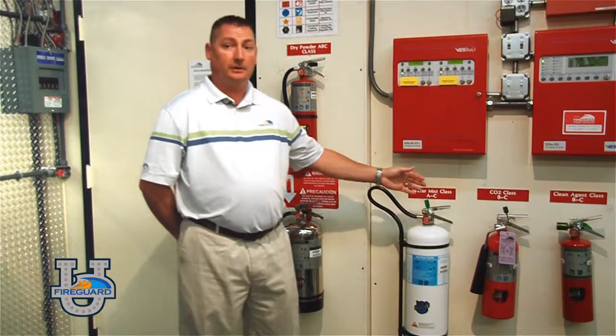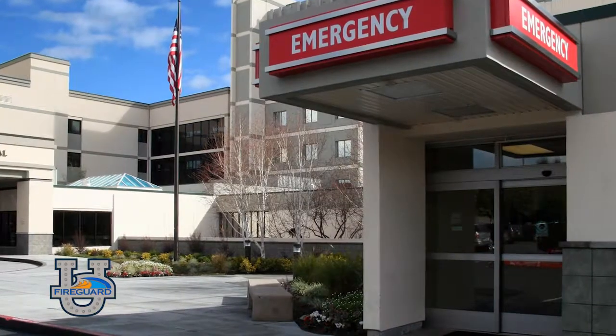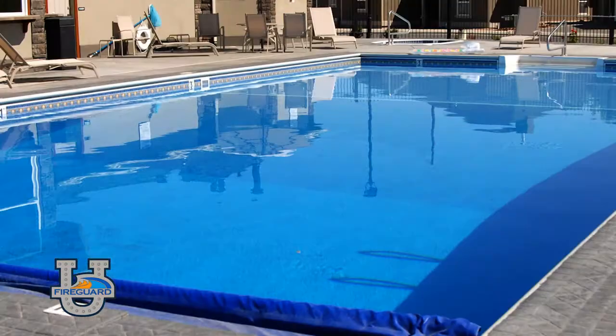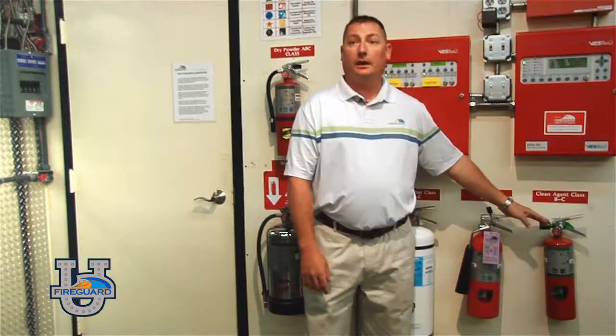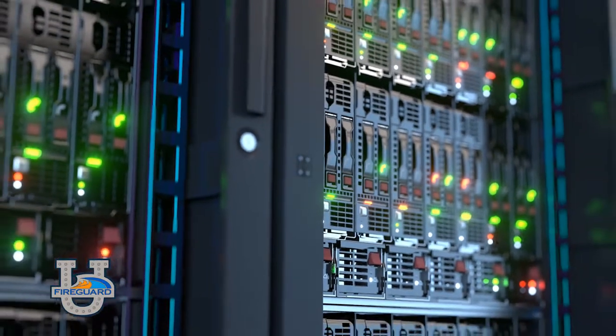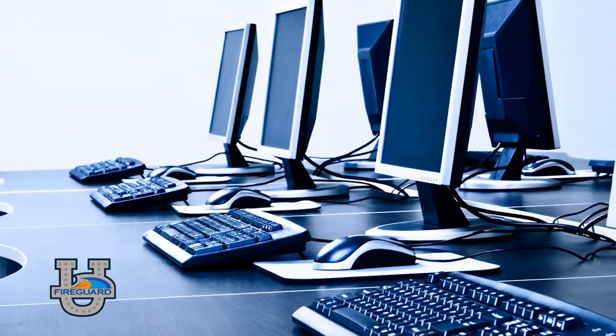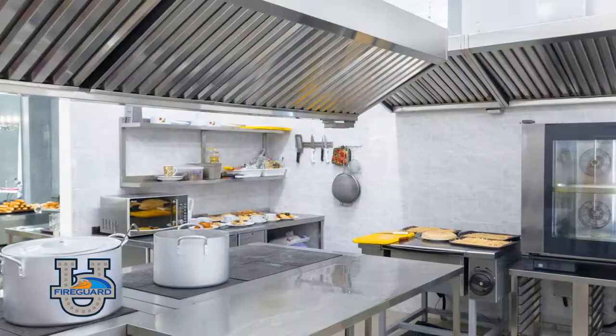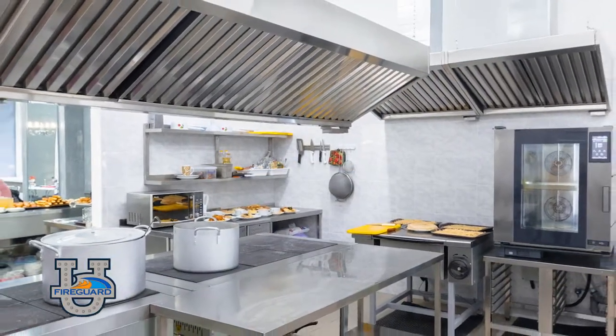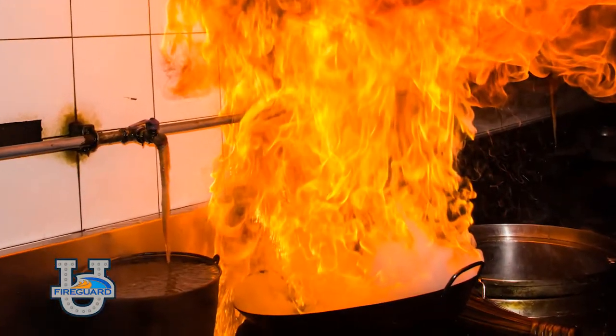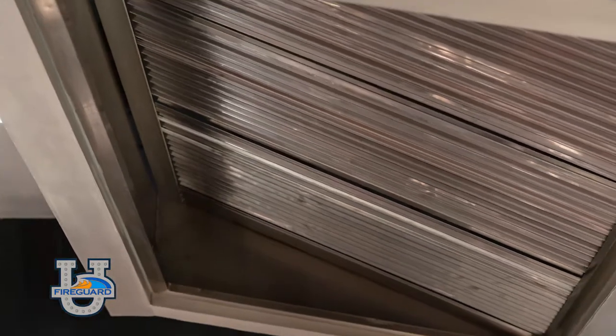The water mist fire extinguisher is most popular with hospitals, museums, and required for all pool chemical storage rooms. Halotron is a clean, non-conductive gas agent suitable for class B and C fires. This is the best unit to protect against sensitive equipment. The class K extinguisher is specifically designed to extinguish kitchen fires involving cooking oils and greases, and is to be used in conjunction with a pre-engineered hood system.